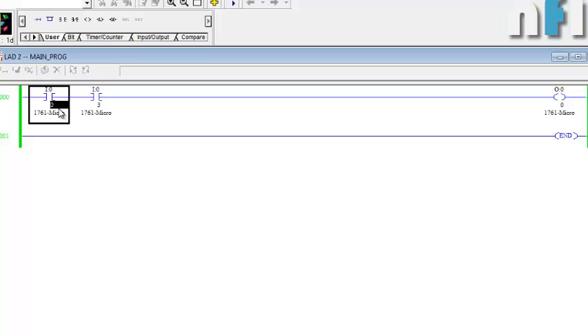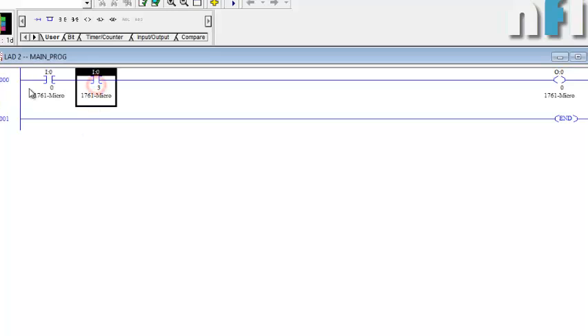Let's download and check it out. Going to run mode now — pressing input I0, you can see on the PLC that the output is not on because I3 is not on. Pressing only I3, the output is still not on. Pressing both inputs, the output turns on — because this is an AND gate: when both inputs are true, output is true.